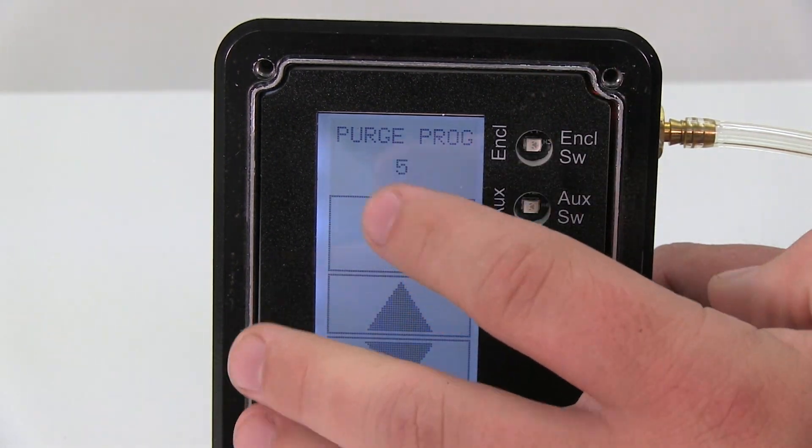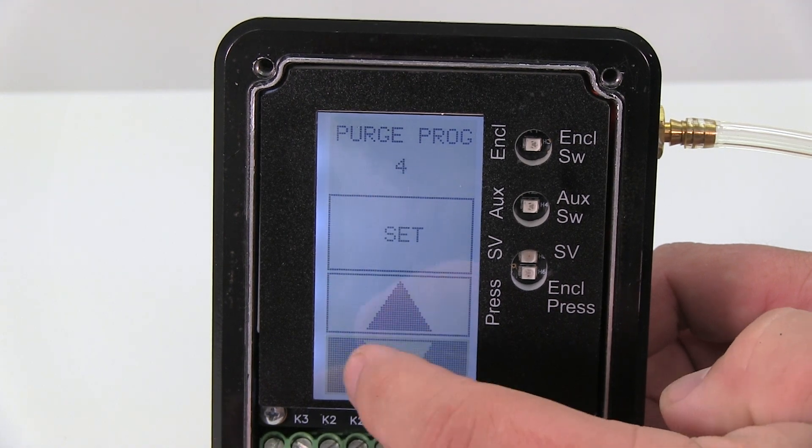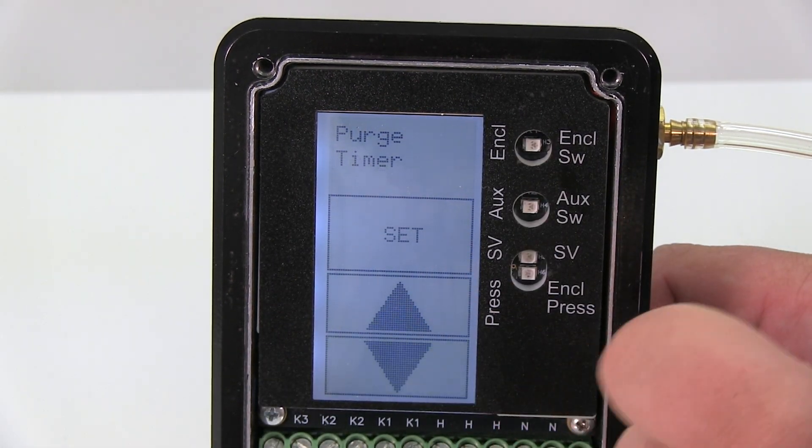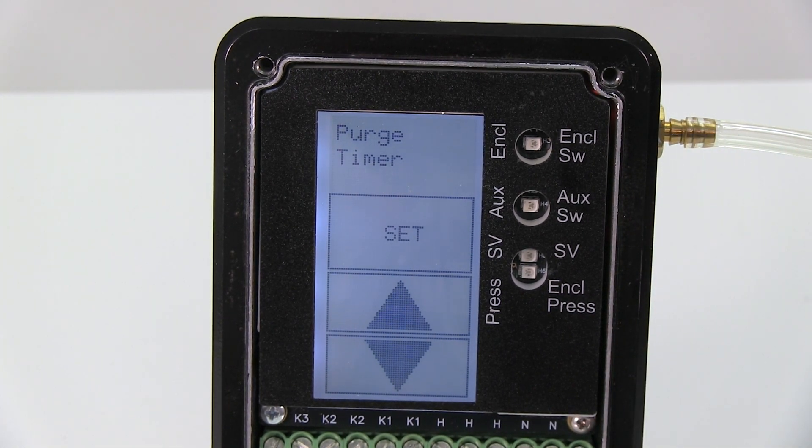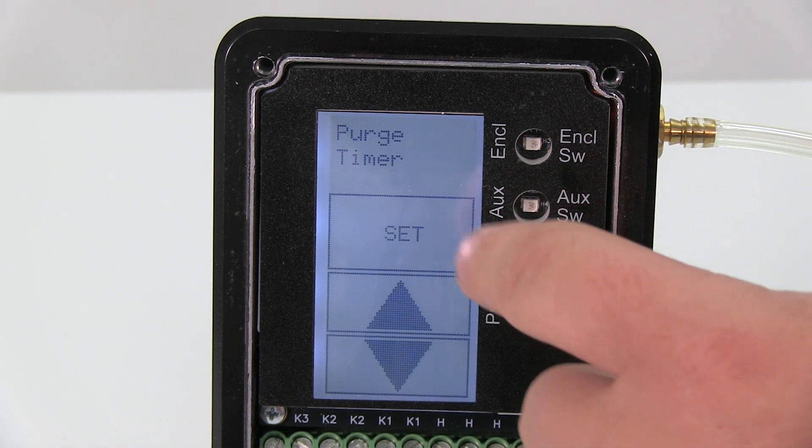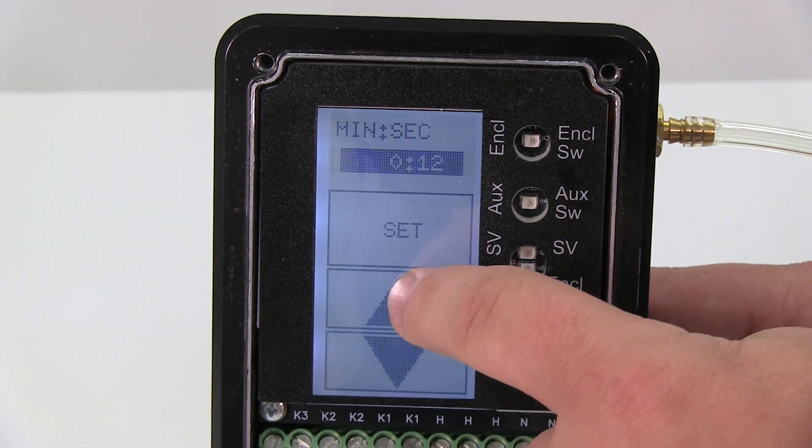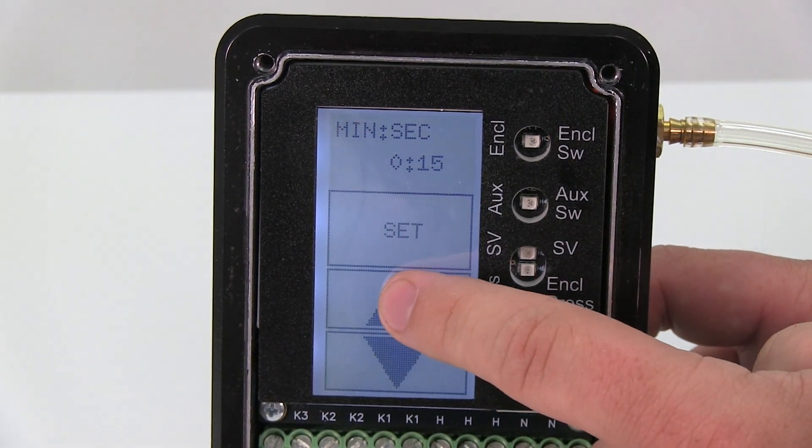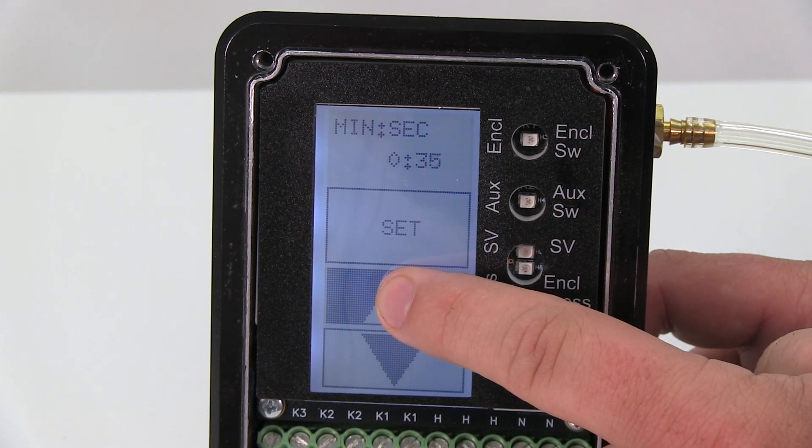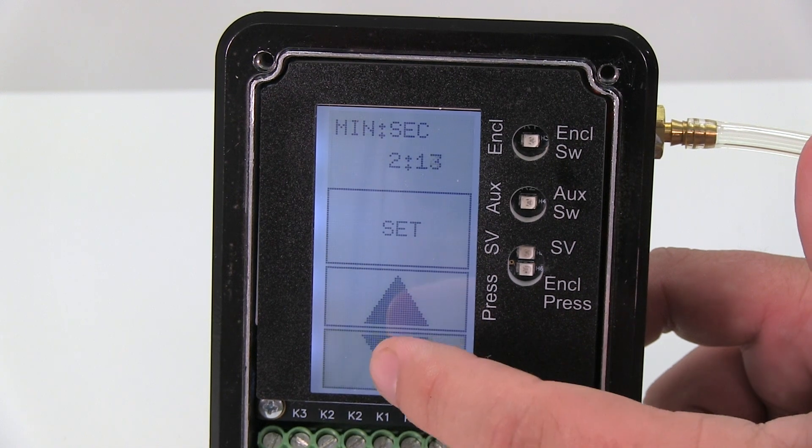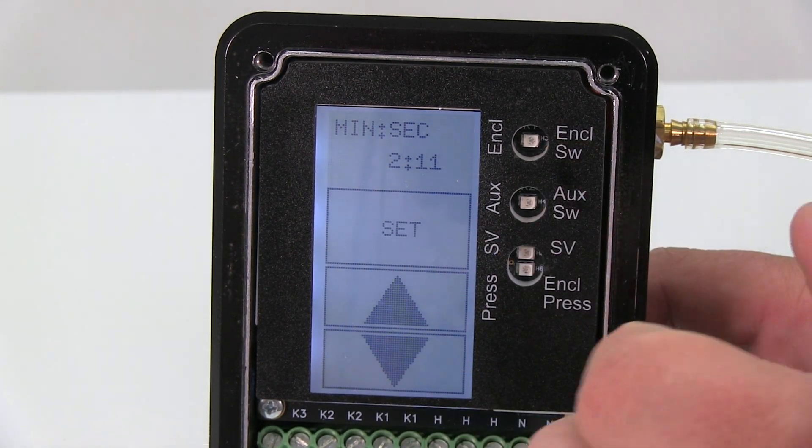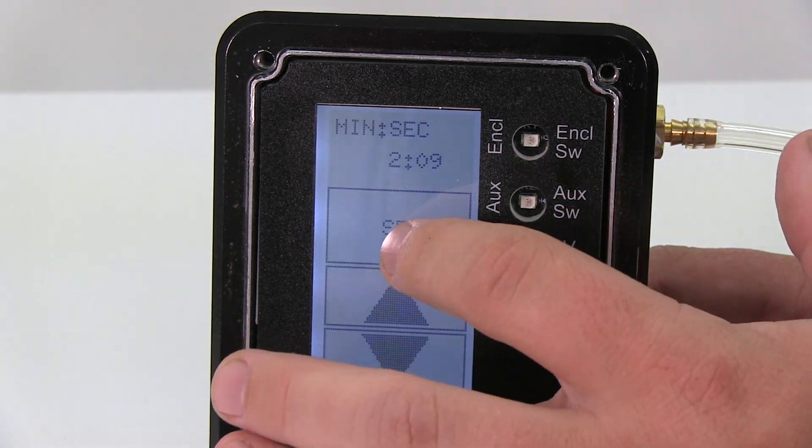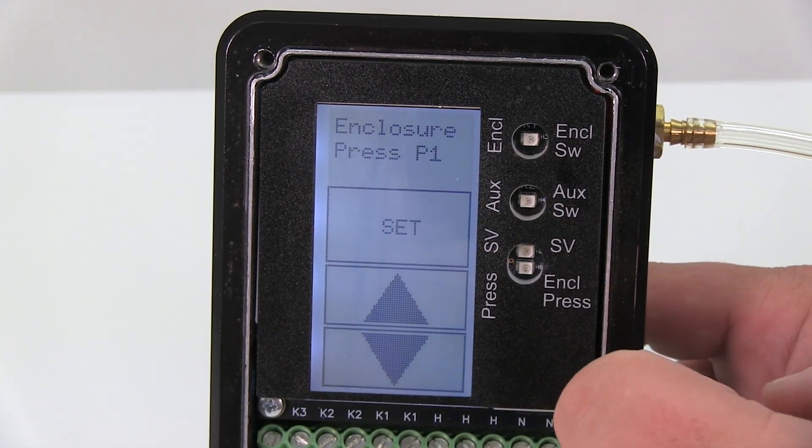Once you pick the program you want - for this example I'm just going to pick program three - the next thing I can go down to is your purging timer. Once you figure out what your purging time is based on the size of your enclosure and the flow rate you're getting, you come in here. I hit set and I can scroll up and down and put whatever time that I need. If you hold an up or down arrow it'll skip by five seconds and then goes faster and faster, but to fine-tune it, you just press and it'll go down by one second. So I'm going to leave it at two minutes and nine seconds - that'll be my purging time.